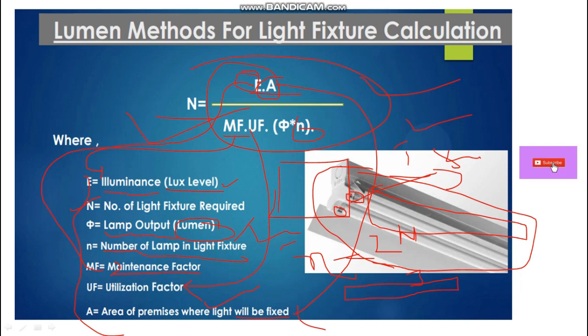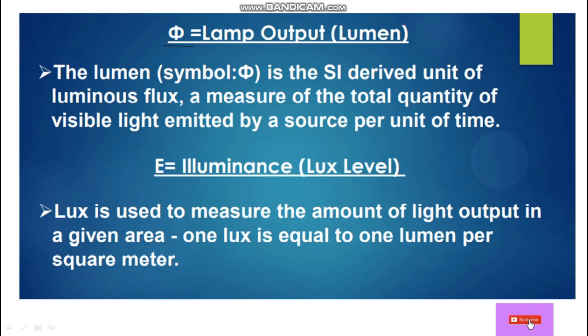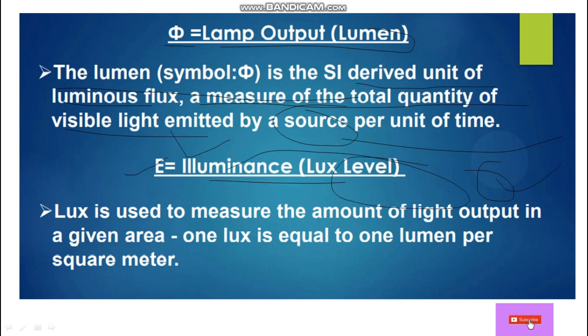Phi (Φ) means lamp output in lumens — the lumen is the SI derived unit of luminous flux, the total quantity of visible light emitted by the light fixture per unit time. E is the illuminance — lux level. For different areas, we have different lux levels. One lux is equal to one lumen per square meter.